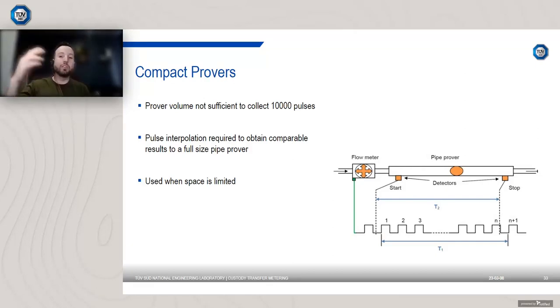Well, whenever the start and the stop detector switches are triggered, this occurs randomly along the meter pulse train. So when you do that, you're actually missing a fraction of a pulse when you start and stop the switch. Now, if you collect 10,000 pulses, that fractional pulse becomes quite a small proportion of the overall pulse count, so it becomes insignificant. Now, what happens if you've got a prover where the volume's not sufficient to obtain 10,000 pulses?